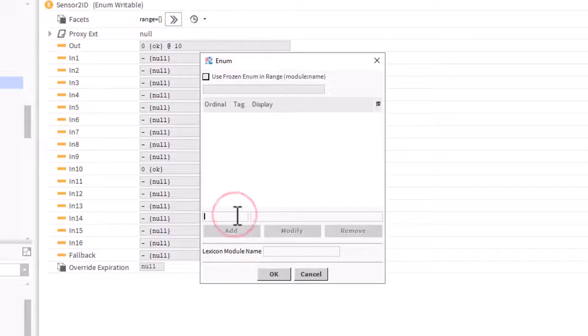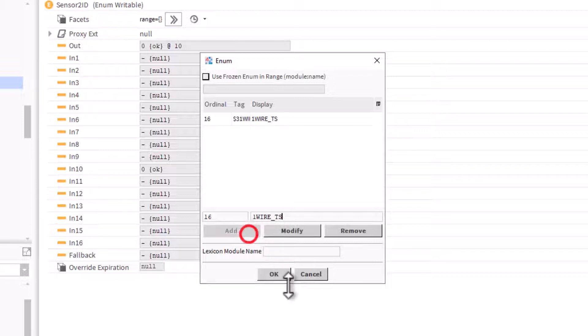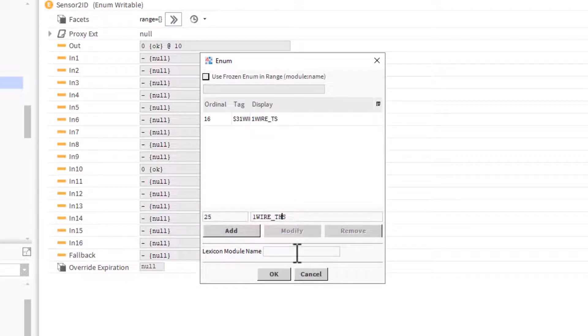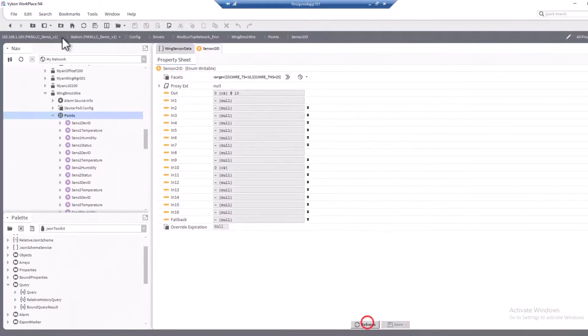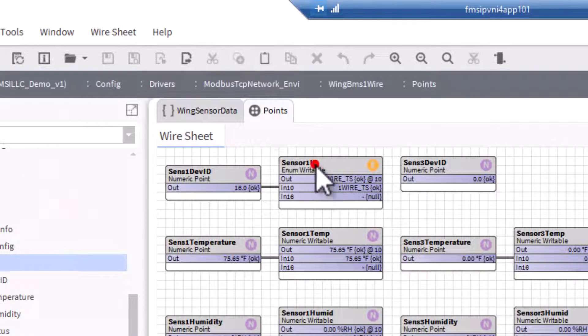Here we're going to put in value 16, which represents the one wire temperature sensor. Click add. Then the next value is 25, which is the one wire temp humidity sensor. Click OK through the dialogs. Save and refresh, then go back. Now we can see that a value of 16 is coming across for the sensor probe plugged into this module, and that 16 is represented as the one wire temp sensor. You can do this with virtually any type of device that's returning different enumerated or numeric values in order to convert it into a logical text.